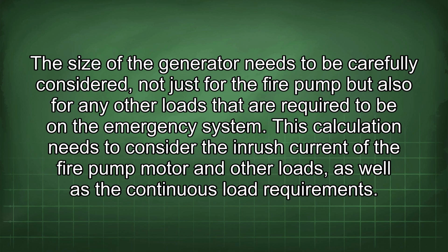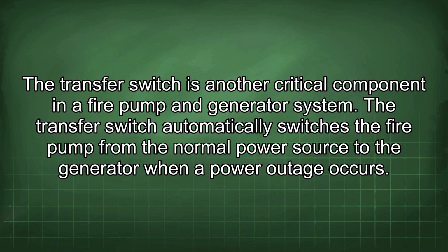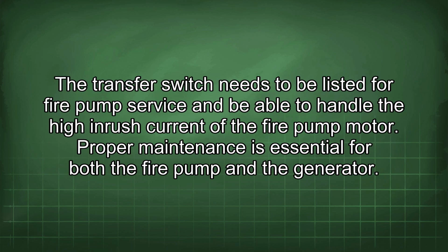This calculation needs to consider the inrush current of the fire pump motor and other loads, as well as the continuous load requirements. The transfer switch is another critical component in a fire pump and generator system. The transfer switch automatically switches the fire pump from the normal power source to the generator when a power outage occurs. The transfer switch needs to be listed for fire pump service and be able to handle the high inrush current of the fire pump motor.